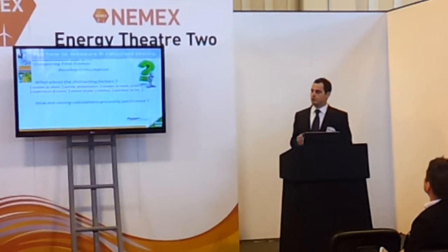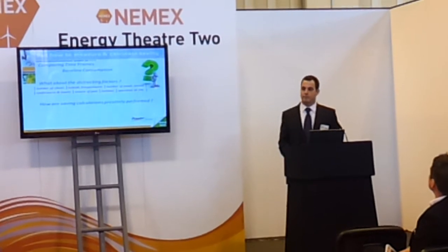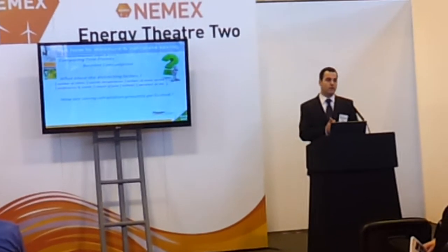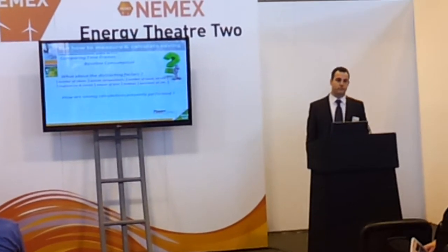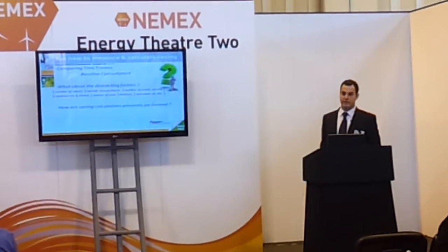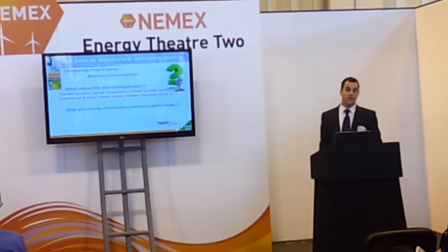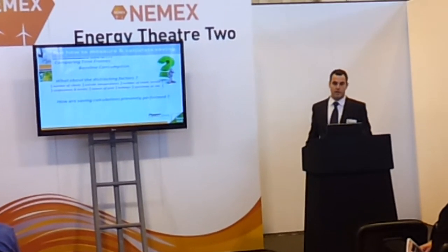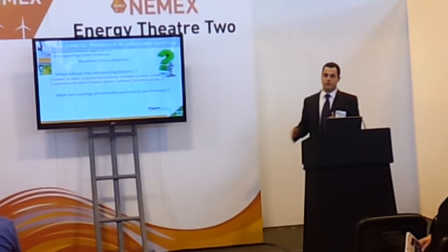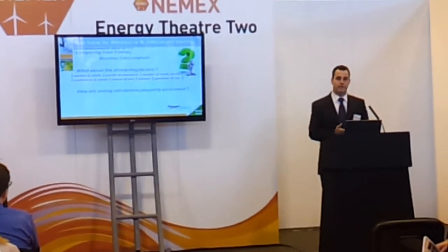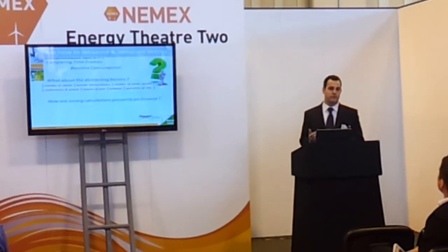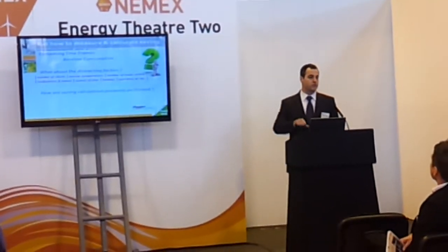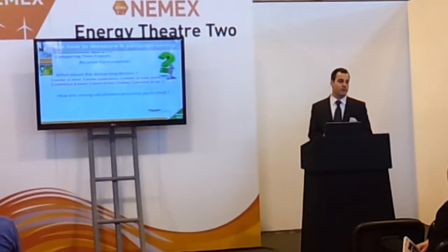That's a huge problem especially when you correlate it into voltage optimization. When you do baseline consumption — a week versus a week — you just extend the effect of all these distracting factors that go into the equation. The statistics becomes quite complicated and less viable and accurate on the whole. And it's obviously impossible to do it on short time increments, because the most accurate way to measure saving is at the point of change. But we cannot do it with most VO systems because you cannot switch sites on and off during operational hours.